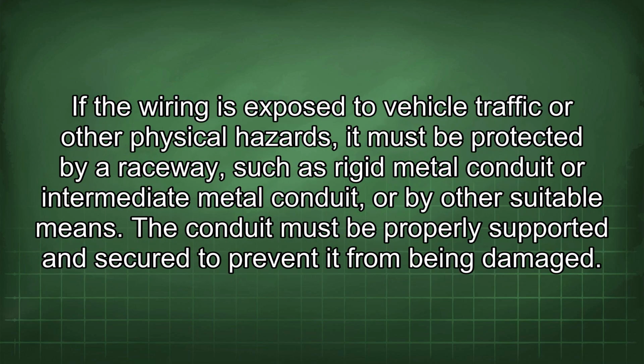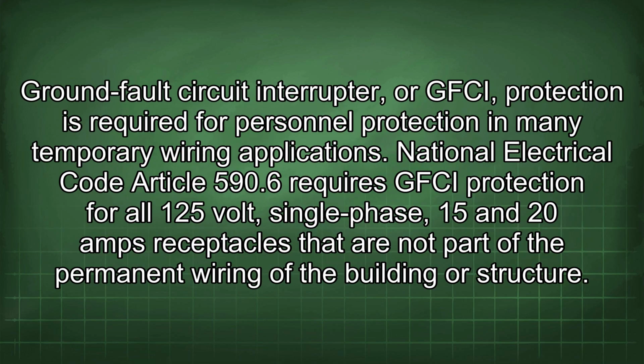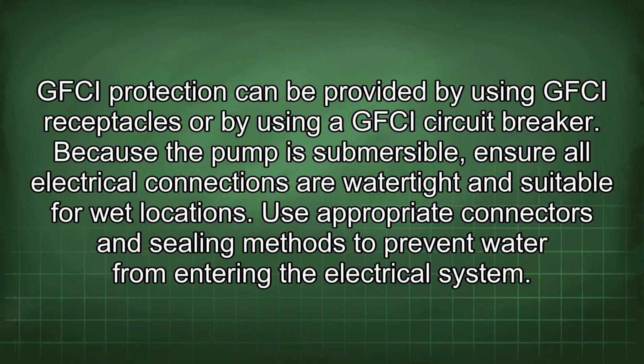If the wiring is exposed to vehicle traffic or other physical hazards, it must be protected by a raceway, such as rigid metal conduit or intermediate metal conduit, or by other suitable means. The conduit must be properly supported and secured to prevent it from being damaged. Ground fault circuit interrupter, or GFCI, protection is required for personnel protection in many temporary wiring applications. National Electrical Code Article 590.6 requires GFCI protection for all 125-volt, single-phase, 15 and 20 amp receptacles that are not part of the permanent wiring of the building or structure. GFCI protection can be provided by using GFCI receptacles or by using a GFCI circuit breaker.